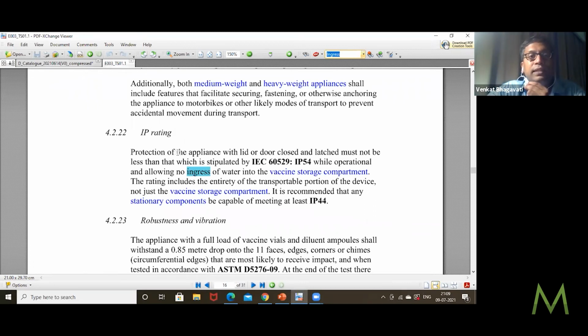So here you have this IP rating. They mention that the protection of the appliance with lid or door closed and latched must not be less than IP 54, which is one of the ratings. And then there is a distinct protocol of how these tests are carried out, like you have to fill the device with the vials and so on, which is in a different document.